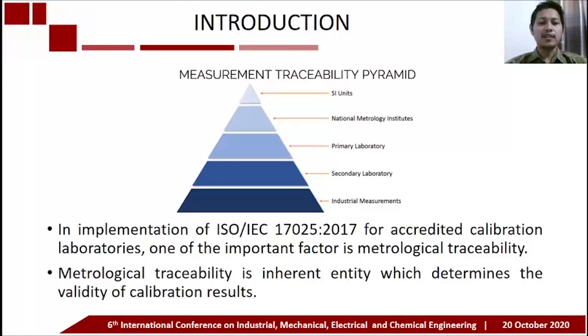In implementing the ISO/IEC 17025 standard for accredited calibration laboratories, one of the important factors is metrological traceability. Metrological traceability is an inherent entity which determines the validity of calibration results. At the top of the pyramid is the National Metrology Institute, which has a primary or national standard, which is the realization of the SI. At the second and third levels are calibration laboratories that have standards traceable to the NMI by calibration. At the lowest level of the pyramid, there are measuring instruments used for measuring activities, such as a ruler to measure length or a thermometer to measure temperature.